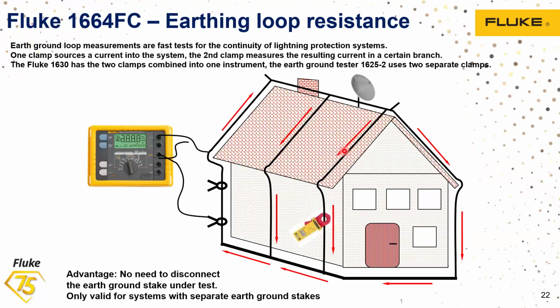And similarly, inside the building, the grounding wires will be everywhere. Though the master earth pit will be somewhere outside the building, internally you will have the loop. Verifying the loop resistance of the earthing is equally important, because if there is a break in the loop and any equipment is installed inside the facility, leakage current starts floating on the equipment, and if anybody touches it accidentally, there is a possible cause of shocks or even serious injuries. To avoid that, checking the loop is equally important.